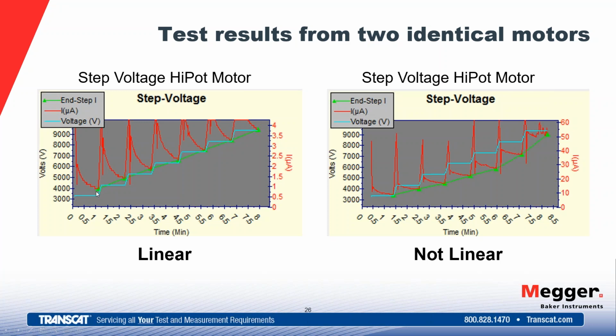What we're reading, again, is current. We take a current reading at the end of that one minute, and then we ramp and raise voltage up again by the same amount each step. We hold for the same amount of time for each step, and then we collect the current value at the end of each one of those steps. So what we expect here is, as voltage changes, current will change, but it should change in the same way. If we're raising voltage the same amount, our current should change the same way.